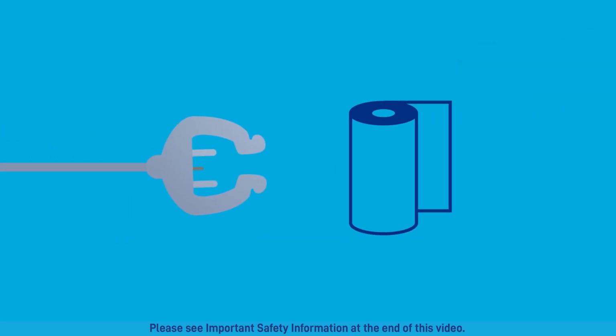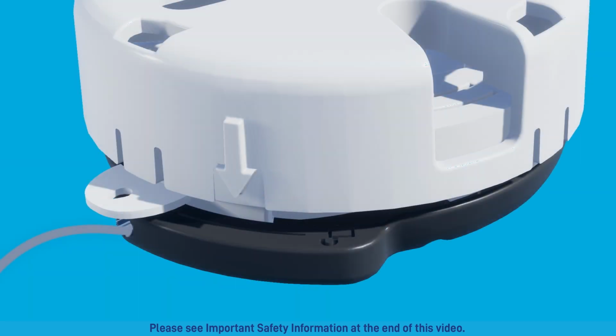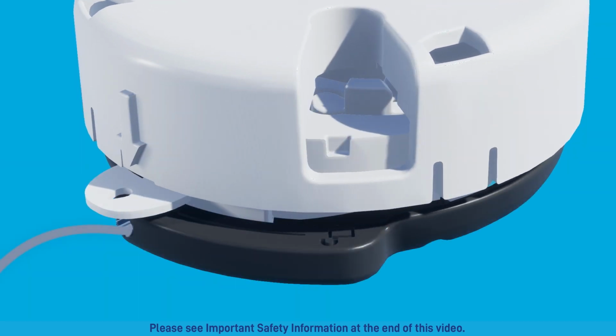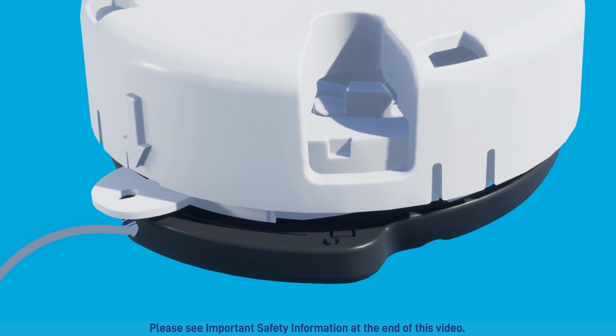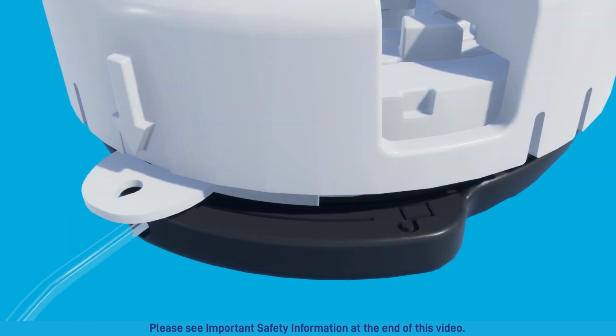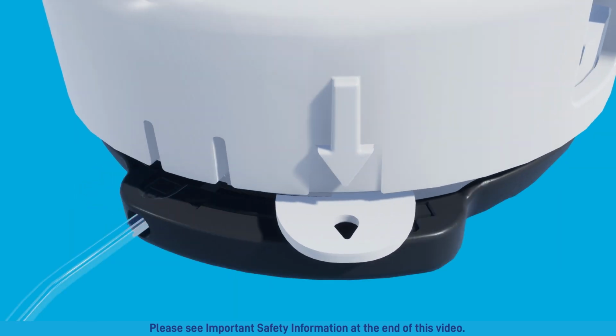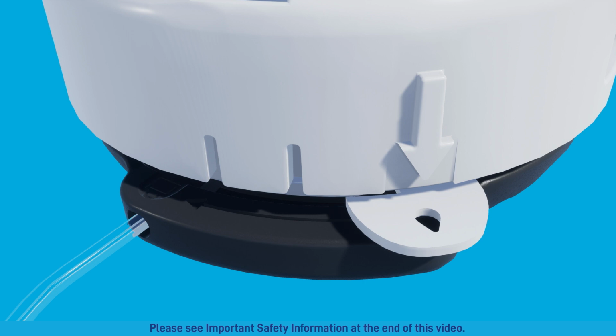Connect the new infusion tubing to the cassette by twisting together. Place the end of the infusion tubing on a folded paper towel. Holding the black side of the cassette firmly, rotate the white top clockwise until you hear a click and the tubing lines up with the droplet symbol. As soon as the medication starts to appear at the end of the tubing, immediately rotate the filling aid back to the left or counterclockwise until the tab on the filling aid aligns with the unlock symbol on the cassette. Your tubing has now been primed.